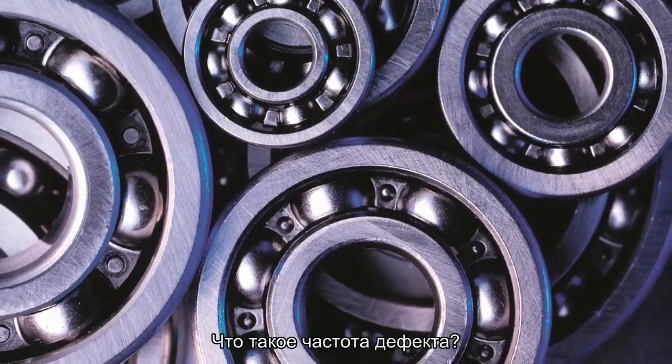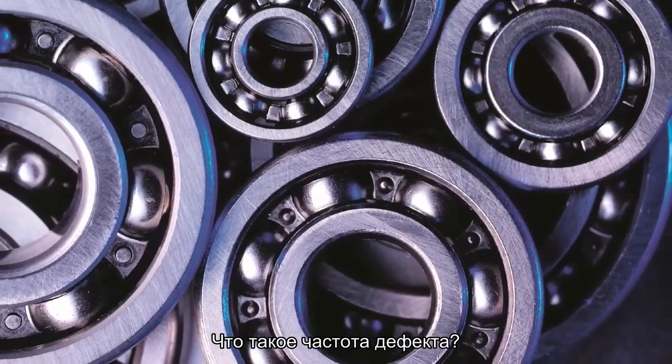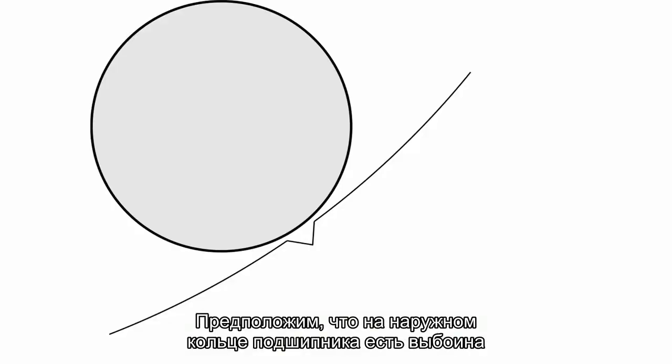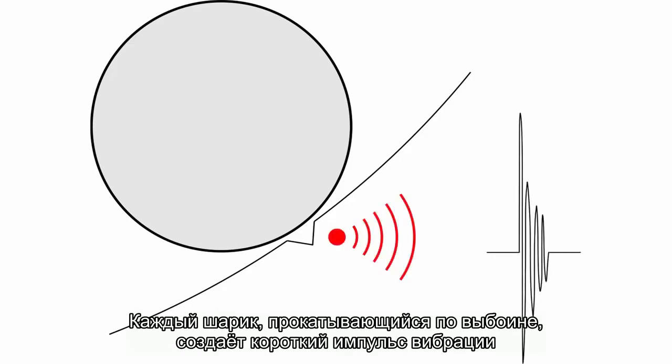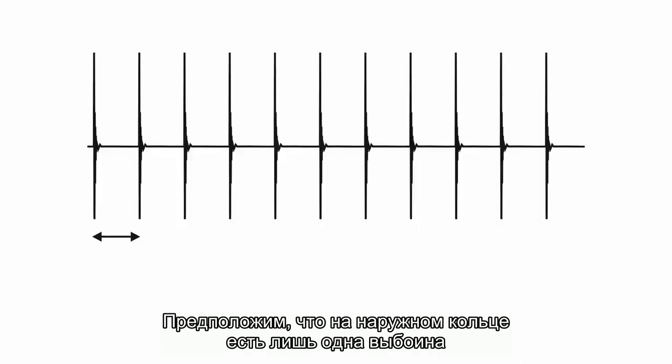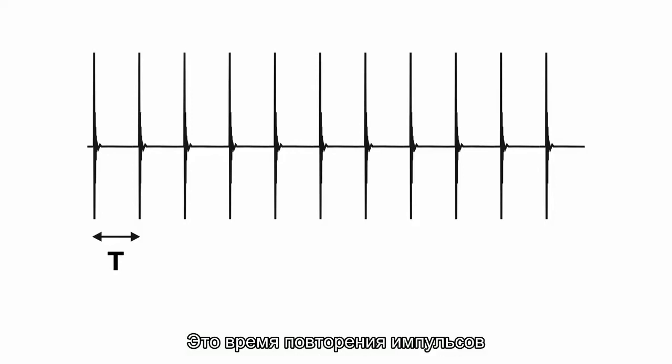What is the fault frequency? Let's suppose there is pitting on the outer race. Every ball passing through pitting causes a short vibration shock. Let's suppose that just one crack exists on the outer race. According to the speed frequency we get the time interval t between shocks. It is the repeating time between shocks.